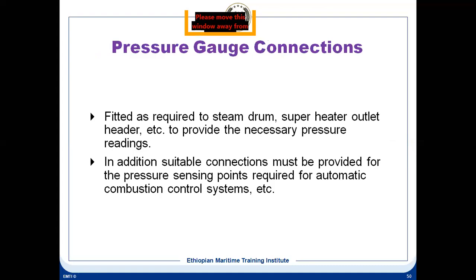And as most of you already know, the pressure gauges which are fitted to these pressure gauge connections, they have to be sent ashore for calibration as per the required periodicity. Definitely during the ship's dry dock or during a boiler survey, these pressure gauges have to be sent ashore to a class approved workshop for calibration.